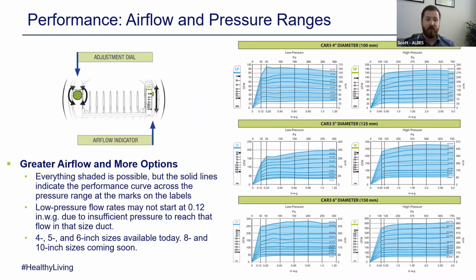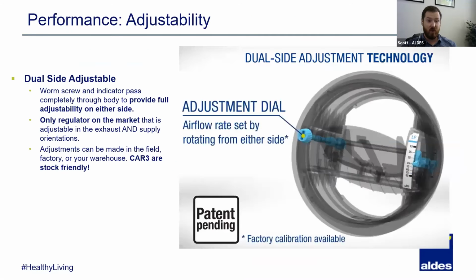Today we have 4, 5, and 6 inch sizes, but very soon we'll be offering 8 and 10. All of those sizes are available in both low pressure and high pressure. Low pressure handles 99% of projects with an operating range of 0.12 to 1.2, whereas high pressure does 0.4 to 2.6 for more special applications. Certainly a bulk of projects will be handled with low pressure.